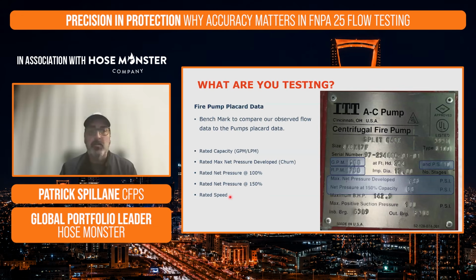And then another key component that we're going to need to make sure we document on every placard is how fast it is rated for, the rated speed. Here, this is listed as RPM at 1,780 revolutions per minute. Again, no matter how we're looking at these, if this is in liters per minute or in bar versus PSI, knowing these details is crucial to making sure that we're doing a proper annual fire pump flow test.